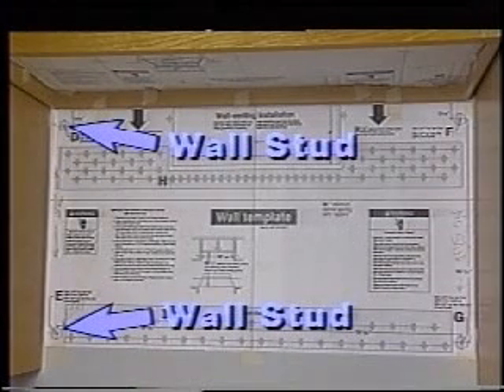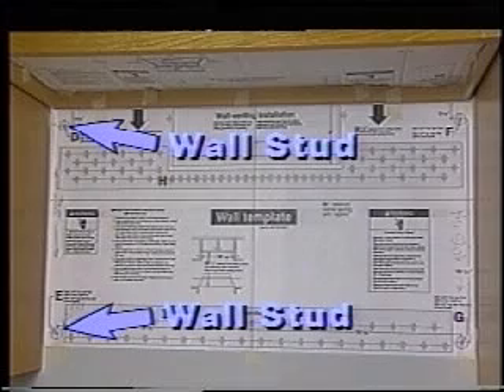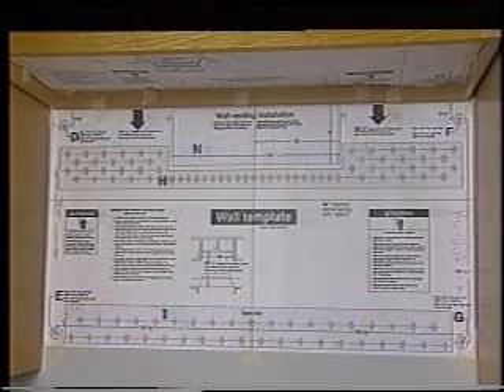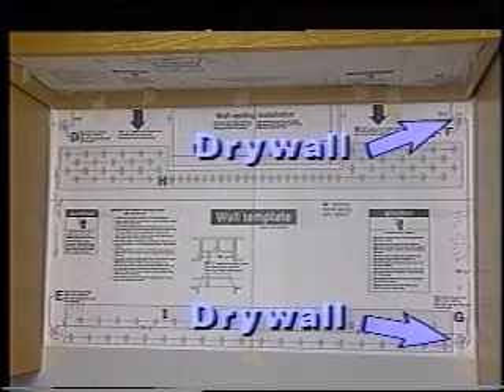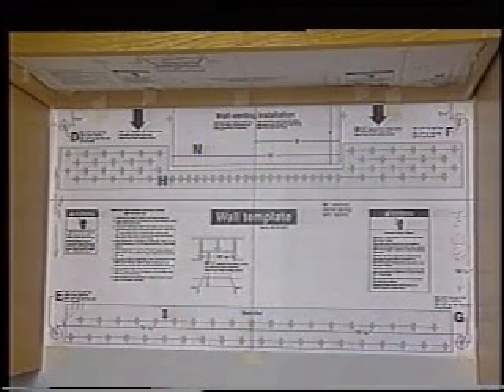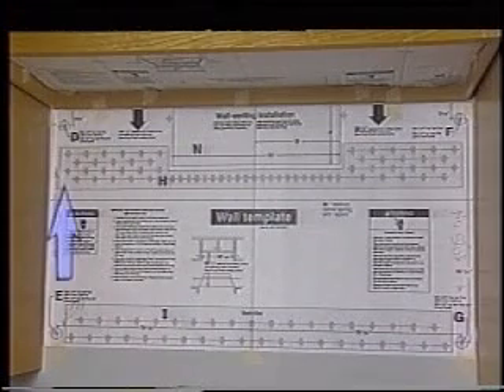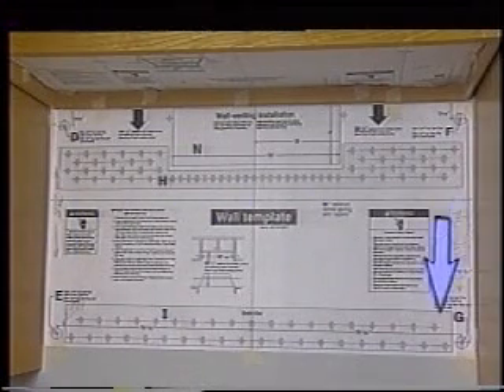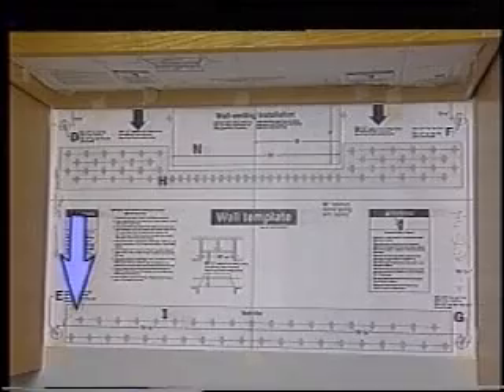Locate the wall studs and mark them on the wall mounting template. In the installation demonstrated here, holes designated D and E are located over wall studs. Holes designated F and G are not over studs. If holes designated D, E, F, and G are not located over studs, a stud must be located and 3/16-inch holes must be drilled, one in area H and one in area I for proper installation.